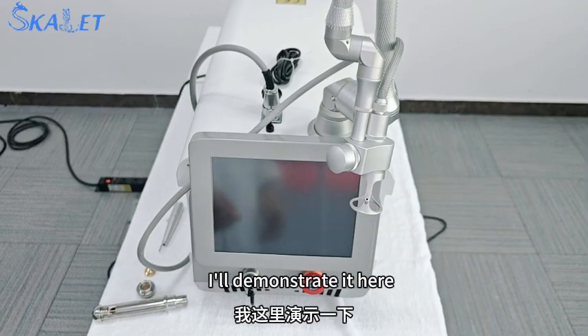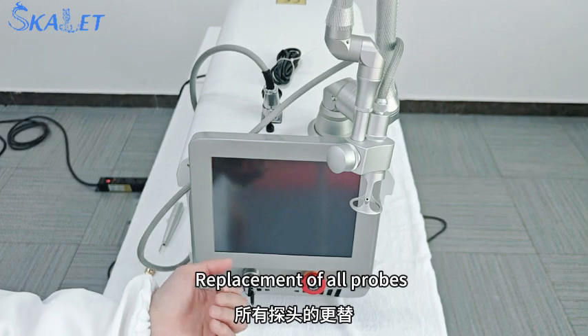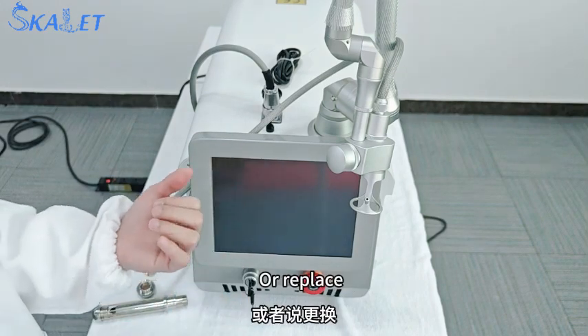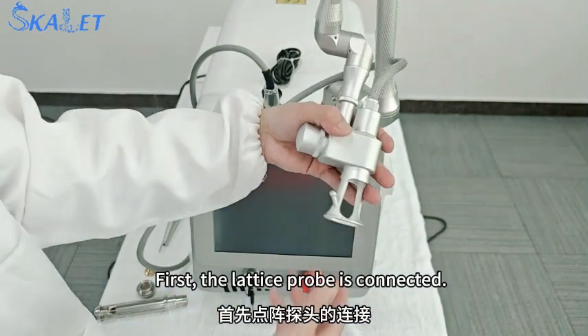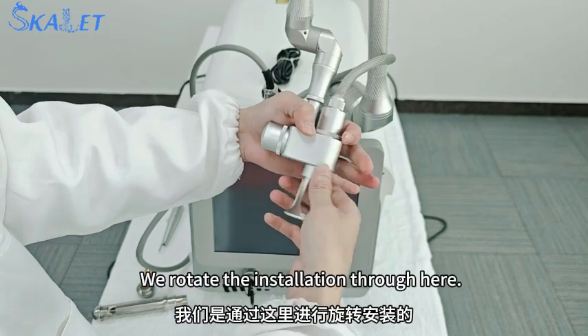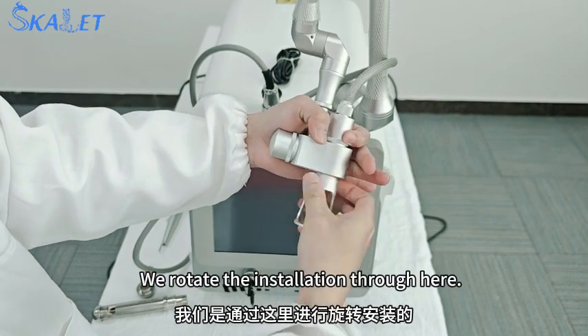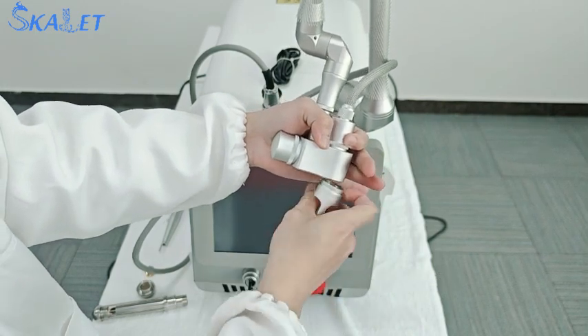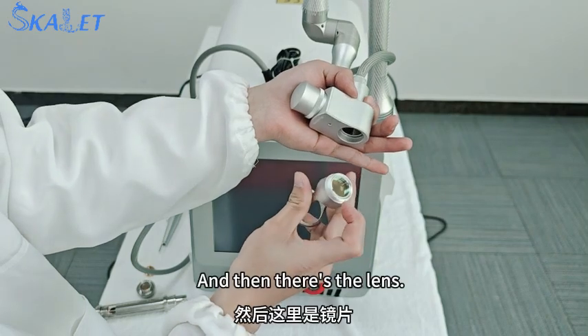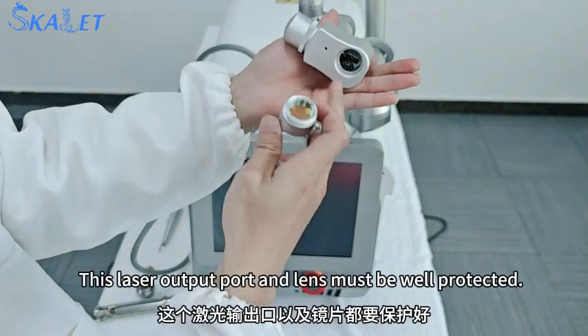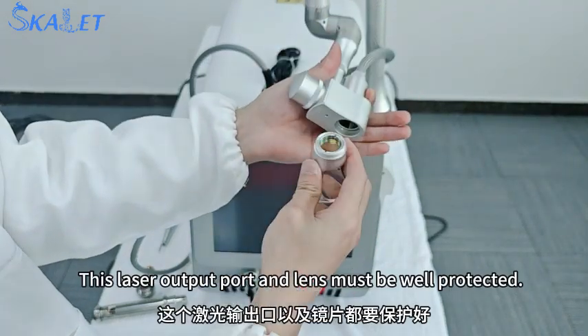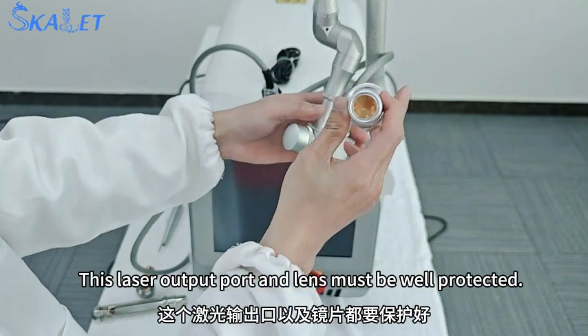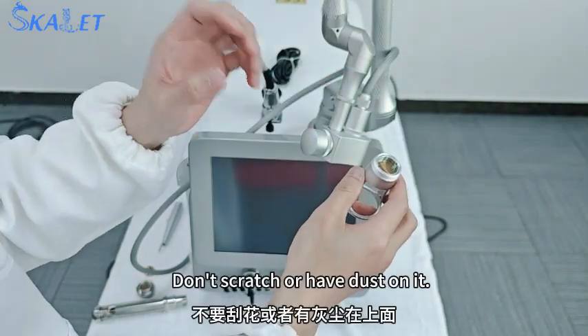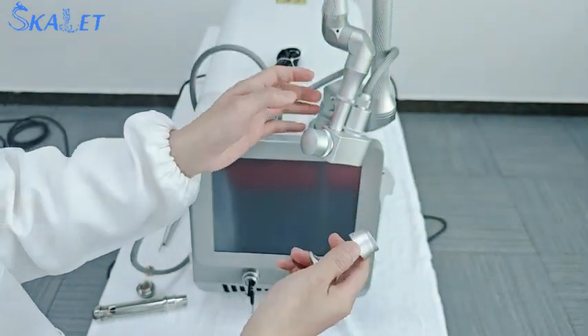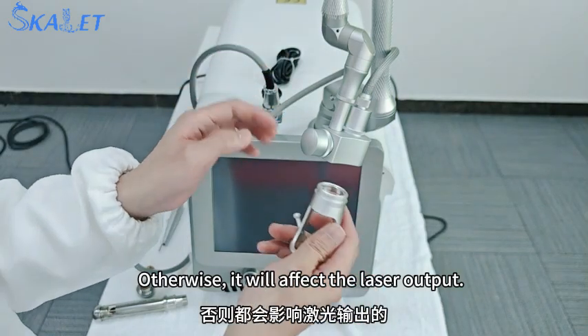Here we go. I'll demonstrate it here. Replacement of all probes. First, the lattice probe is connected. We rotate the installation through here. It can be removed. And then there's the lens. This laser output port and lens must be well protected. Don't scratch or have dust on it. Otherwise, it will affect the laser output.